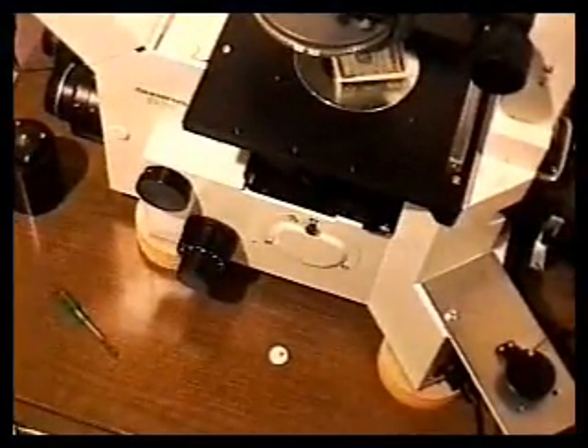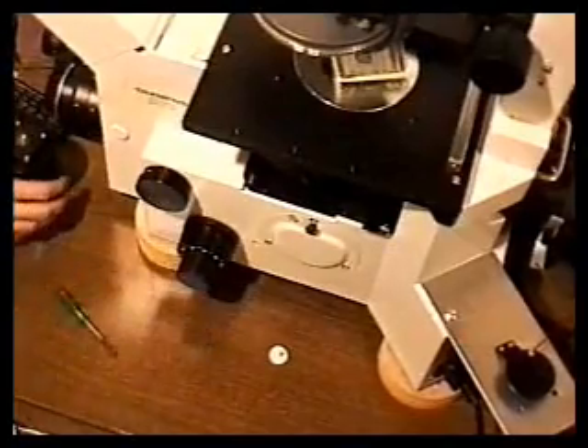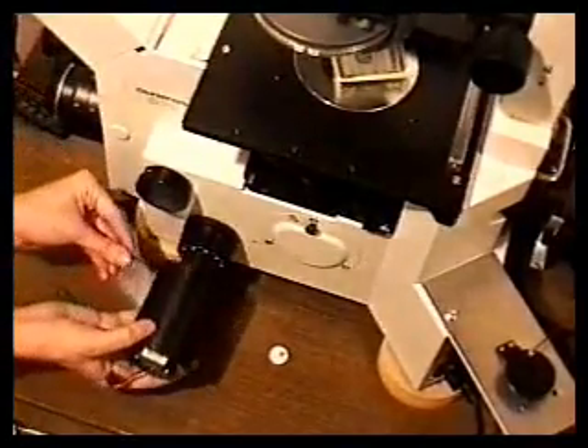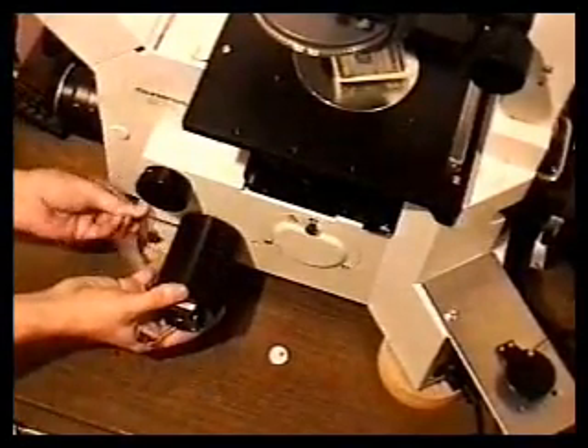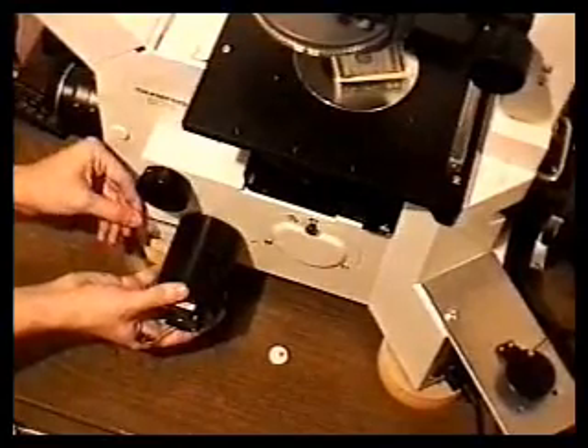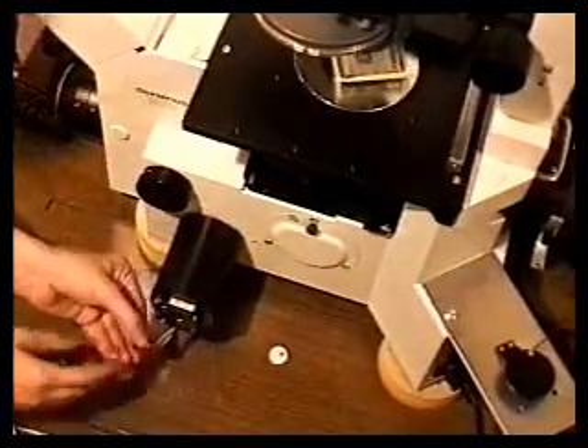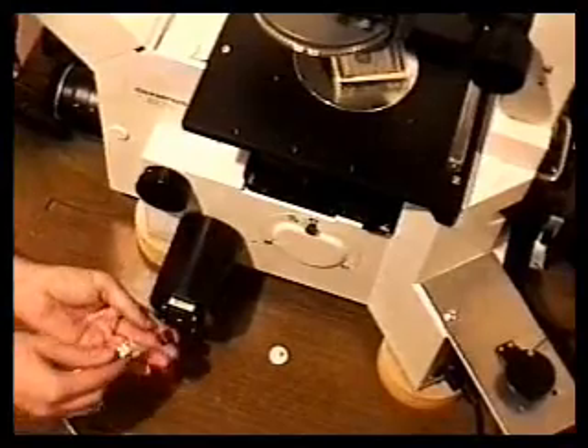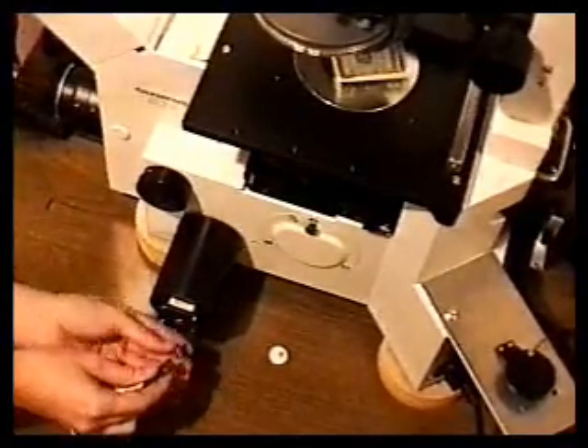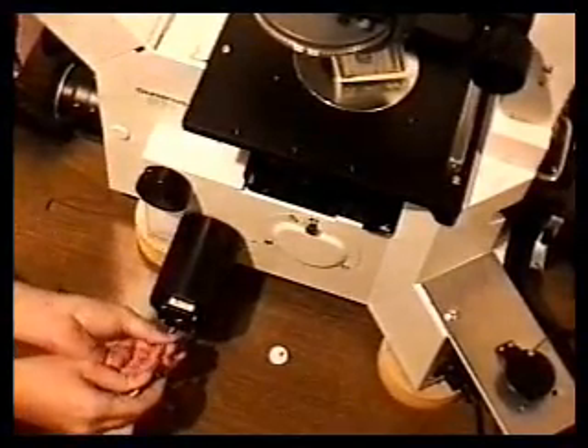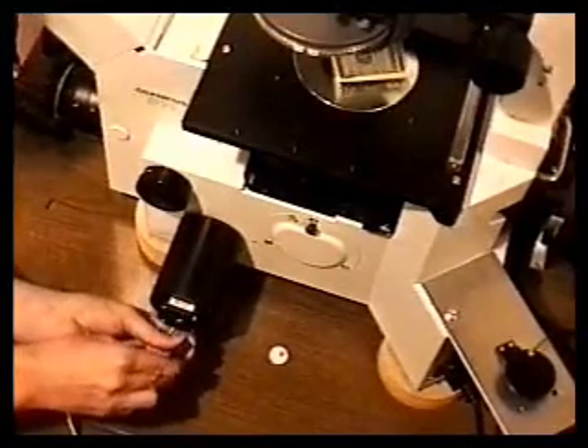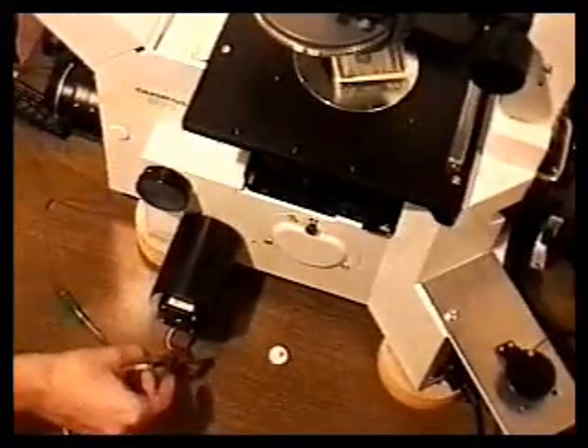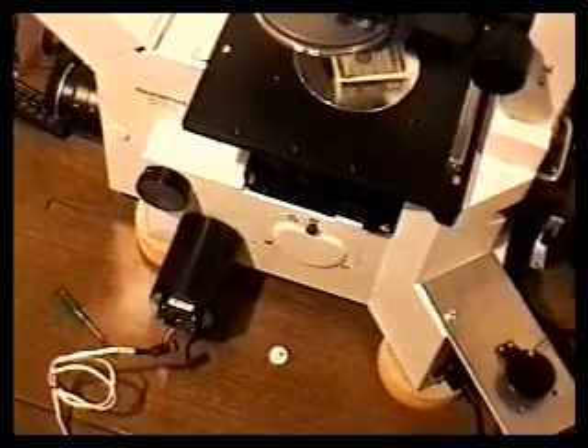So here's the focus knob of the microscope, and all we do is take the focus controller, slide it over the knob, tighten it with an Allen wrench, and attach its connector to the 4-pin connector coming from the RoboScope master control unit, and make sure that the black and yellow wires go as marked. And now that one's all set.